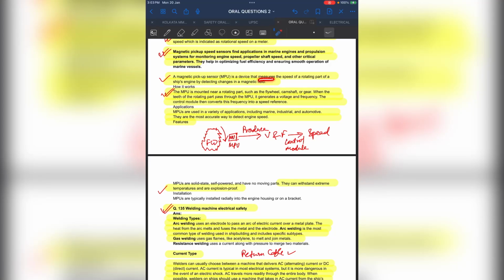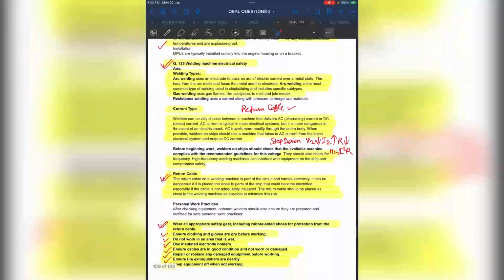So the magnetic pickup sensor is a device that measures the speed of a rotating part of a ship engine by detecting changes in the magnetic field. The MPU is mounted near the rotating part such as a flywheel, camshaft or gear. When the teeth of the rotating part pass through the MPU, it generates a voltage and frequency, because there is a change in flux. Whenever there is an induced voltage, it has its own frequency, and the control module then converts this frequency into a speed reference. So these are the basics.